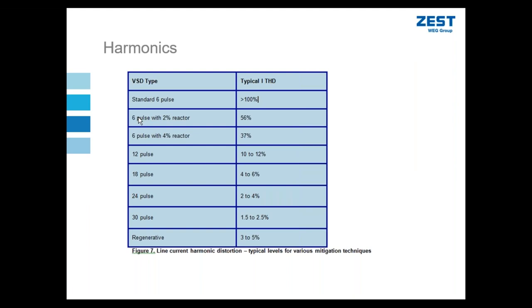I can take that same drive, that same diode rectifier, and put a 2% reactor at the input of that device, and that will make a massive improvement and bring me down to 56%. I can increase the voltage drop of that reactor, that choke at the input of the drive, and you can see again a very large benefit that will bring me down to the 36-37% mark that I showed in the previous slides.